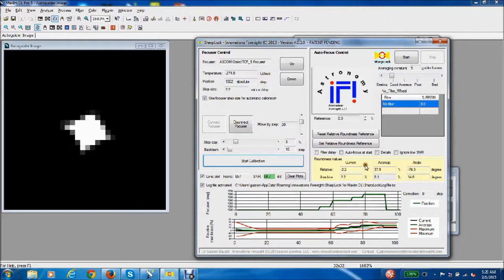the bottom plot, the value is outside the red limit, and in that case the system doesn't update the average anymore. Which means we have to move the focuser again a bit up in order for the system to start to change the relative roundness average. This happened because we have a very good seeing and we move by a lot the focuser and changing by a lot the roundness. As soon as the roundness goes back in the red limits, the average will be updated.